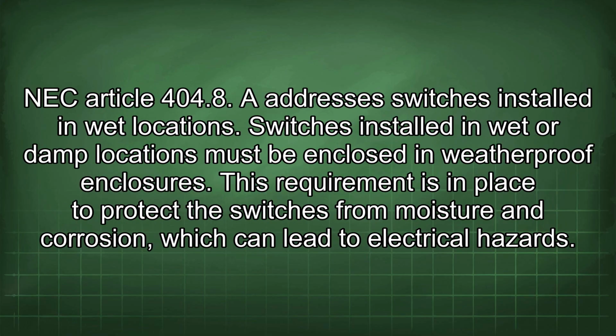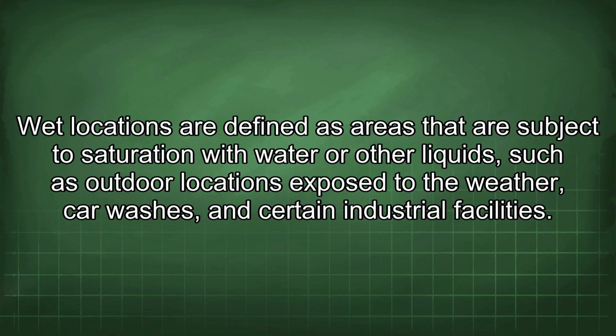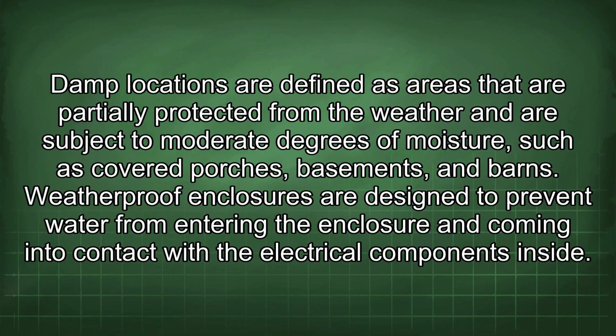NEC Article 404.8 addresses switches installed in wet locations. Switches installed in wet or damp locations must be enclosed in weatherproof enclosures. This requirement is in place to protect the switches from moisture and corrosion, which can lead to electrical hazards. Wet locations are defined as areas that are subject to saturation with water or other liquids, such as outdoor locations exposed to the weather, car washes, and certain industrial facilities. Damp locations are defined as areas that are partially protected from the weather and are subject to moderate degrees of moisture, such as covered porches, basements, and barns. Weatherproof enclosures are designed to prevent water from entering the enclosure and coming into contact with the electrical components inside.